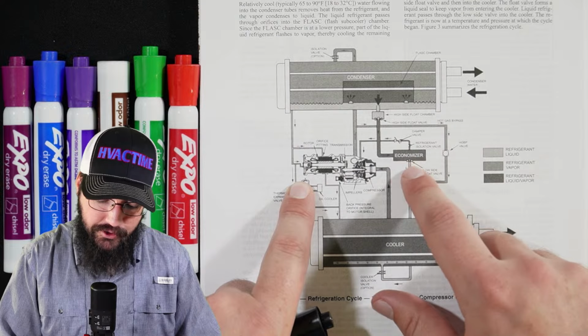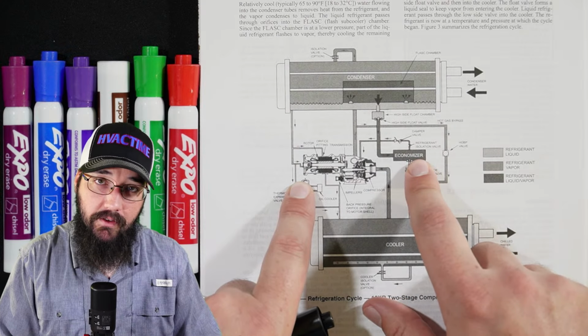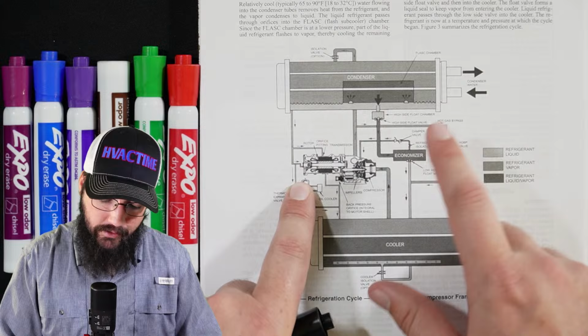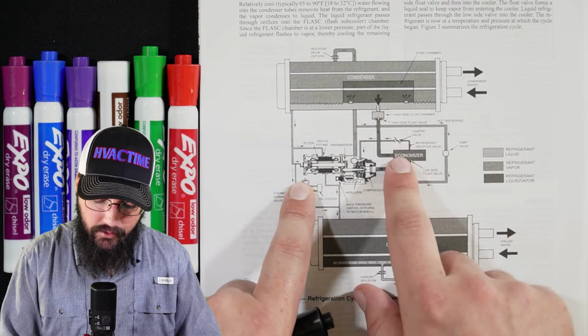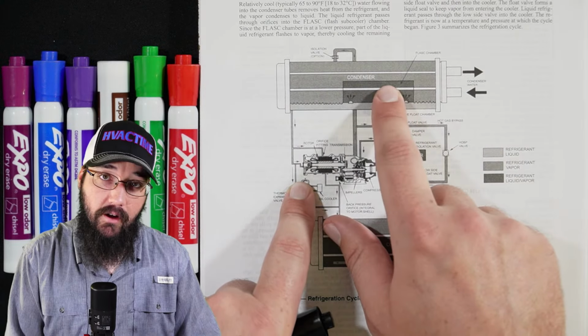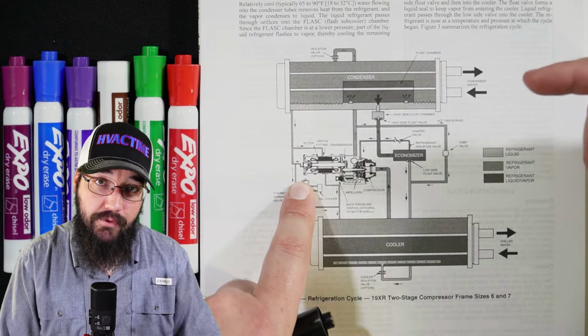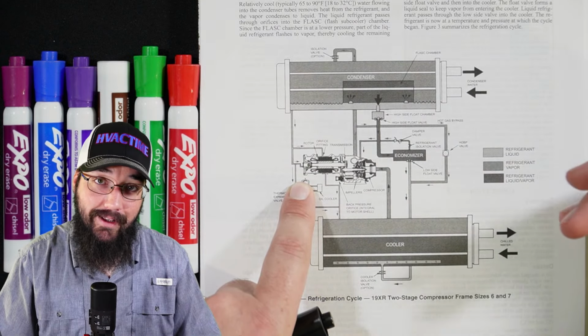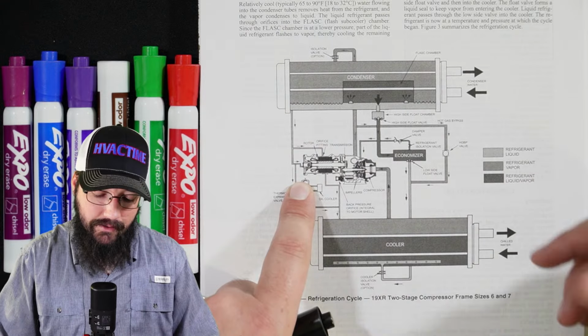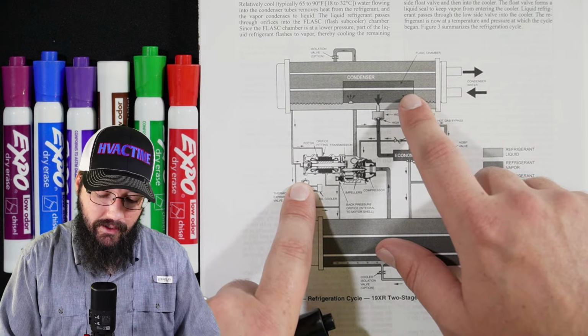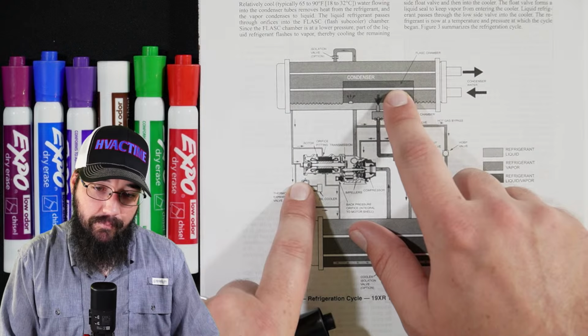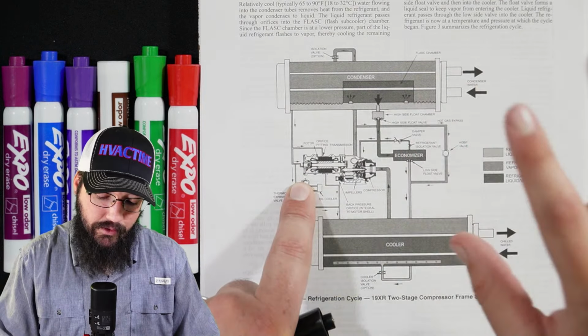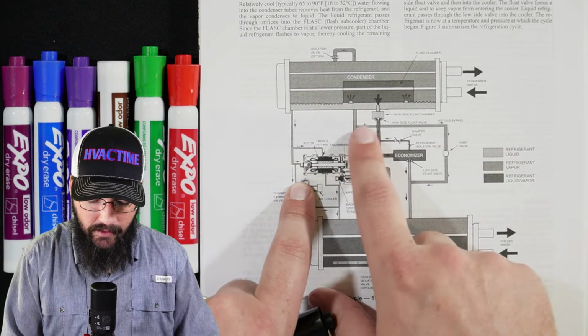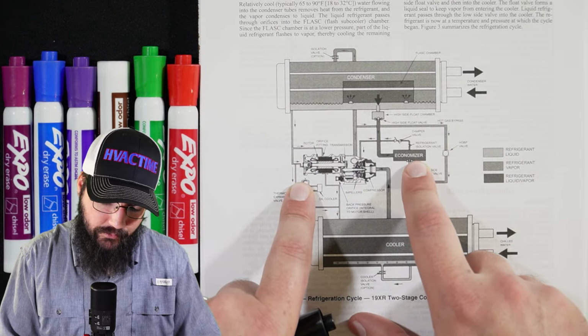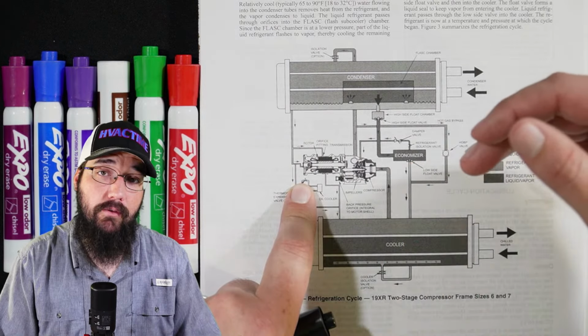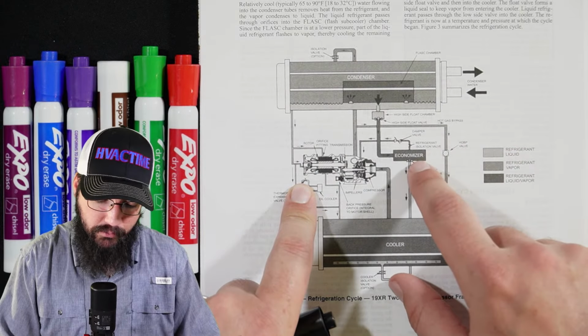There's no other heat exchange happening inside of this side of the economizer. And in Carrier's literature, they're not going to call this an economizer, even though if you read the description, they're describing what is a flash tank economizer, in my opinion. They're not going to call it that. They'll call it the flash chamber, and fair enough, it's not the traditional economizer design. And then they go into what they actually call the economizer. That's how they will reference this.